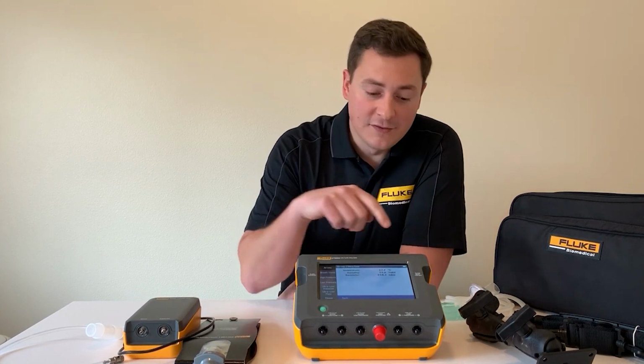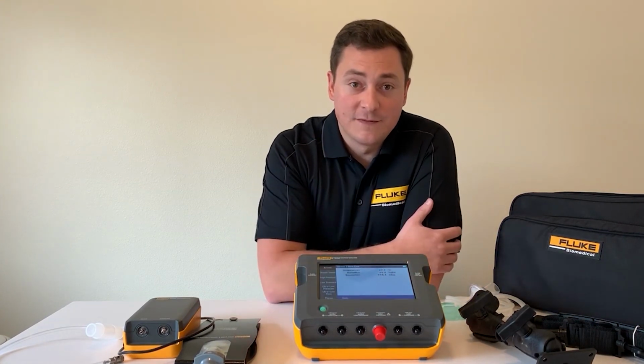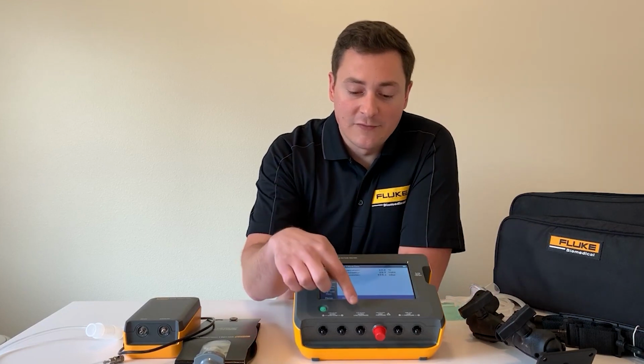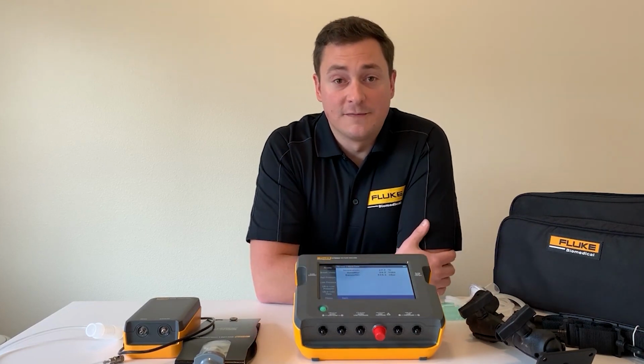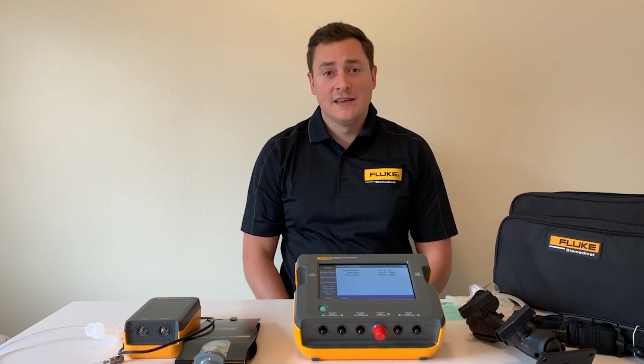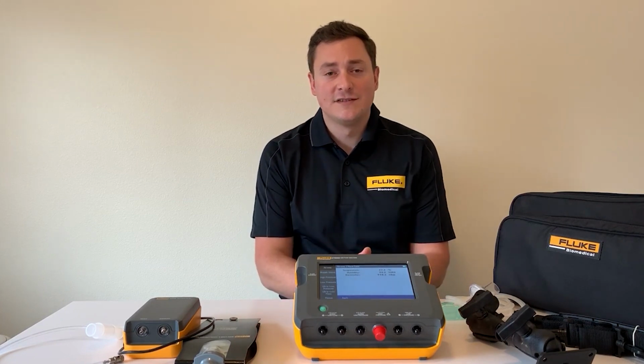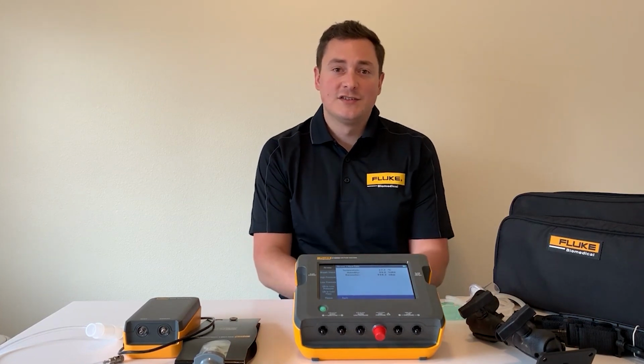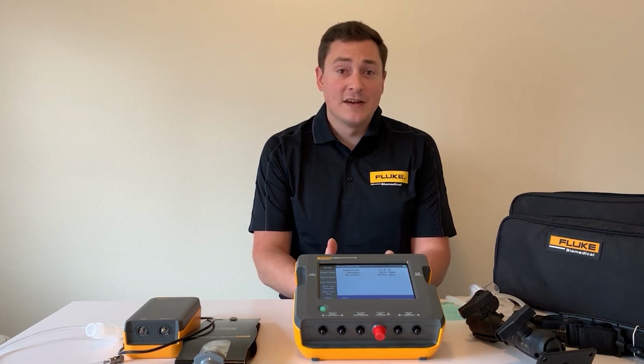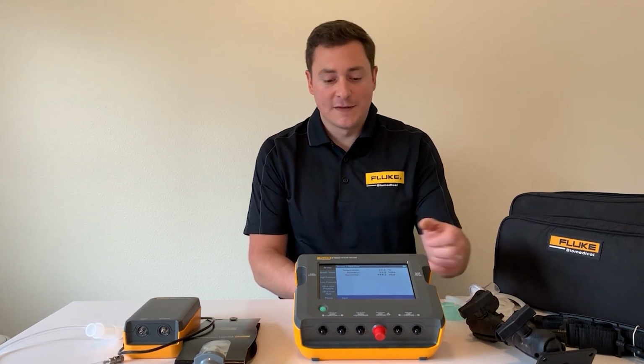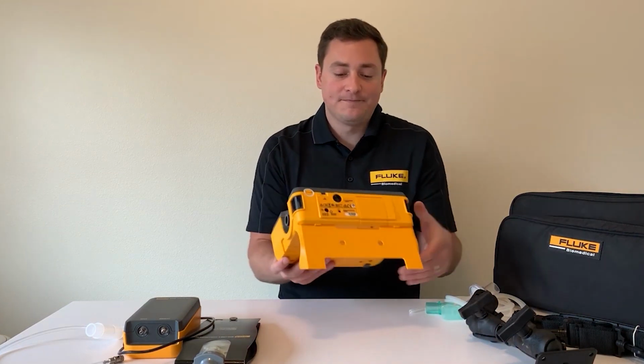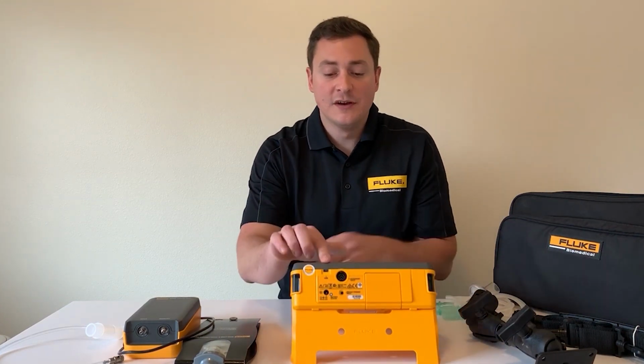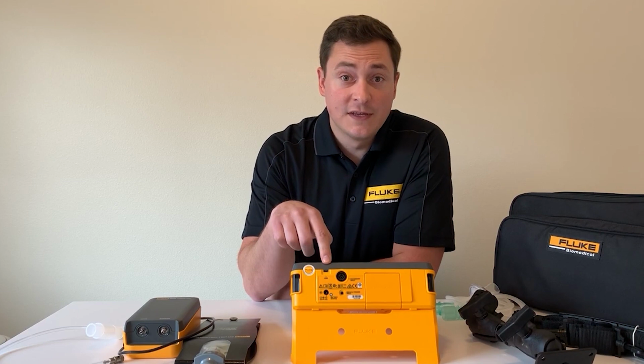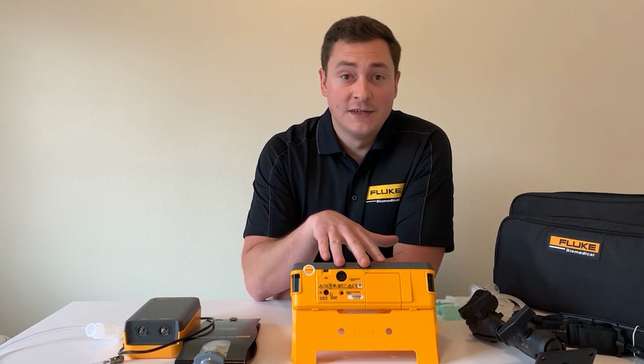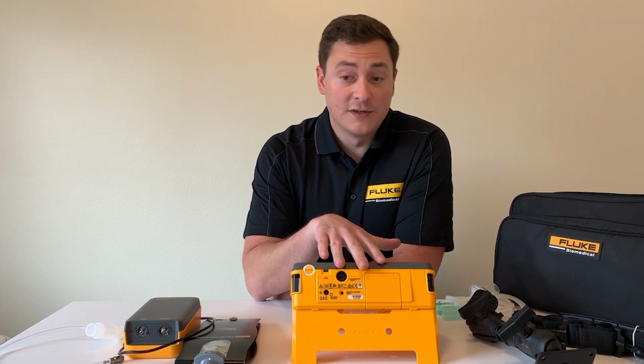If we move to the front of the unit, we have low and high pressure ports here at the front, available on both models. And then we have ultra low pressure and ultra low flow here at the front. This is available on the VT900A and gives you higher fidelity, higher accuracy measurements for applications such as oxygen concentrators or anesthesia machines. So that's when you're going to want to think about that. If we move to the back of the unit, we have a USB port here where you can pull off your test results because there's onboard memory on this unit as well as an 8-hour battery. So this is truly an all-day, on-the-go tester.